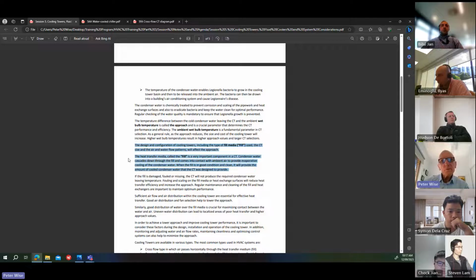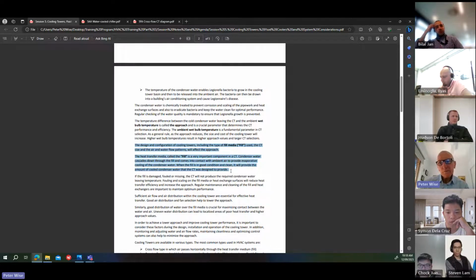The heat transfer media, called the fill, is a very important component in a cooling tower. Condenser water cascades down through the fill and comes into contact with ambient air to provide evaporative cooling of the water. When the fill is in good condition and clean, it will provide the amount of cooled condenser water that the cooling tower was designed to provide. So when the cooling tower is brand new, everything's nice and clean. It's been designed to achieve the performance that you want, the water flow, the leaving temperature of the water, and so on.